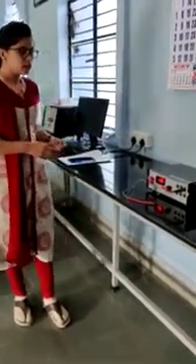So now we see its actual method. In normal mode there are two methods used, that is the manual data logging method and the auto data logging method. In the software we first select the experiment mode, such as normal mode, and then select the data logging method, that is either the auto data logging method or the manual data logging method. Then data logging is generated, meaning there is a reading, date, time and temperature logged as per the method selected.